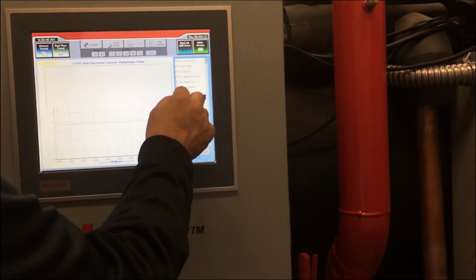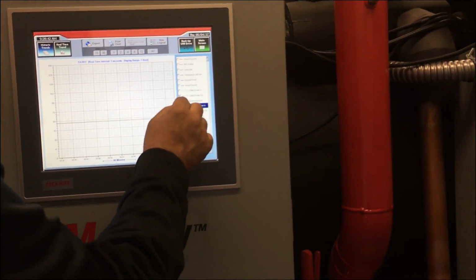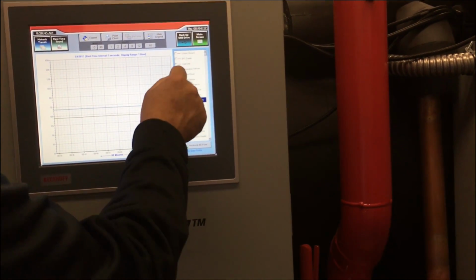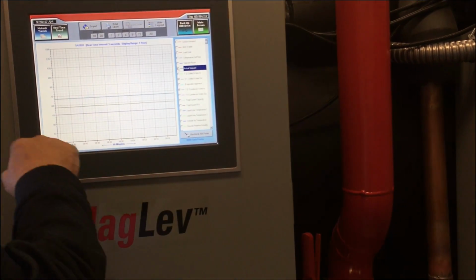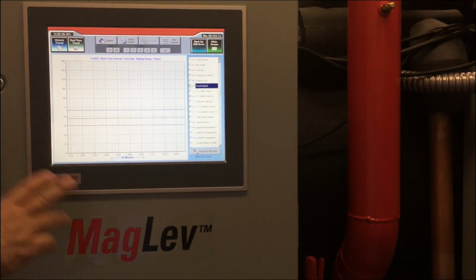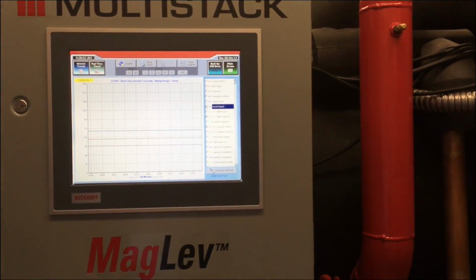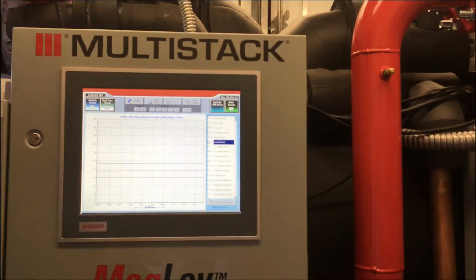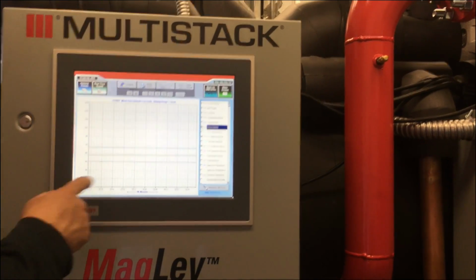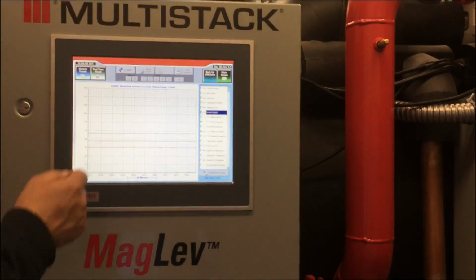I like to take chill water out. I'll usually go condenser water in, so the 2 I really care about. Then I'll take actual set point, and I'll watch what happens with those 3. Those are the first 3 I go at, and then from there I may look at the BAS enable, to see if they're taking it away and adding it. That's either 100 or 0 because it's on or off.